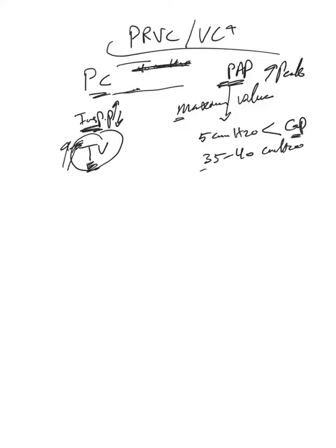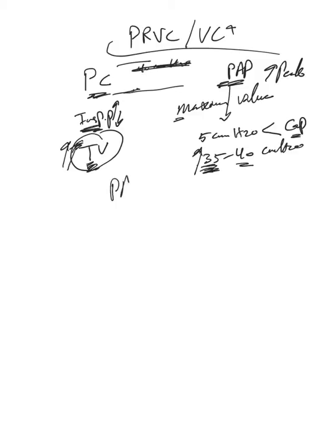The ventilator keeps changing its pressure target until it reaches this number and then it will not go higher than this, despite that. That way we guarantee proximal airway pressure in this mode will never go above 35, for example, or whatever maximum value we set.